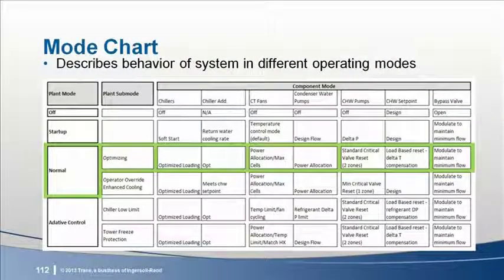As for the operator, a system mode dashboard that actively shows not only the operating mode the plant is in, but also the operating set points and conditions for key system components should be available. Think of this as a real-time sequence of operation that helps the operator understand precisely how the system is supposed to be operating, and therefore, if it's operating properly. Experience has shown this, too, can be a positive step towards sustained performance.